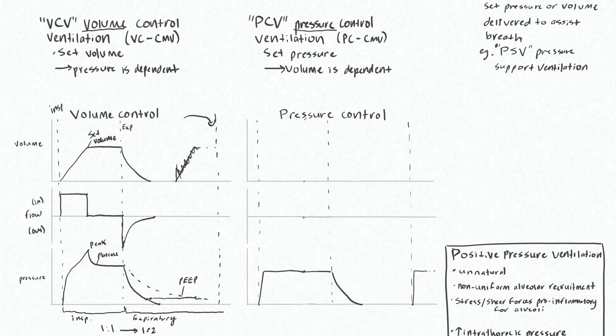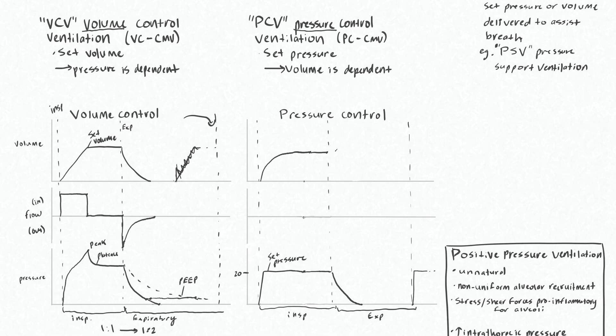With a pressure control mode, you're setting your pressure — let's say 20 centimeters of water. All throughout your inspiratory phase, you're quickly brought up to this 20 centimeters of water of pressure, and then the ventilator holds you at that pressure for the entire inspiratory phase until it's released and pressure decreases during the expiratory period. The result is a non-linear increase in volume of your lungs, which at some point stays the same because you no longer have flow. If we add PEEP, the end pressure stays at maybe 5 centimeters of water rather than going to zero.